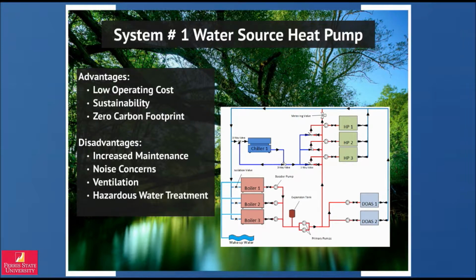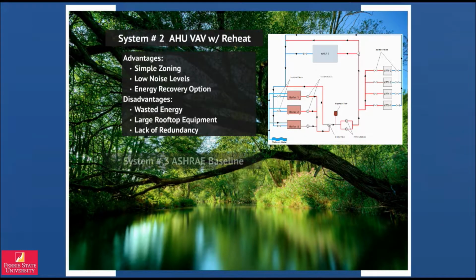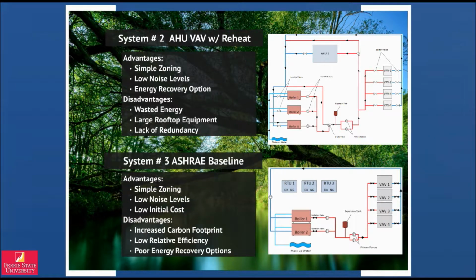When considering geothermal as a source of energy, the New York Department of Environmental Protection sets restrictions and regulations involving city water supply, water tunnels, shafts, and other city resource lines. Avoidance of subway and mass transit tunnels were also taken into consideration. Due to the close proximity to these underground mass transit systems and resource obstacles, geothermal was eliminated as a potential source of energy for the heat pumps. The next 2 systems analyzed were a variable air volume system with reheat and the ASHRAE baseline system, which consists of packaged rooftop units and VAVs with reheat, direct expansion cooling, and fossil fuel hot water boilers.